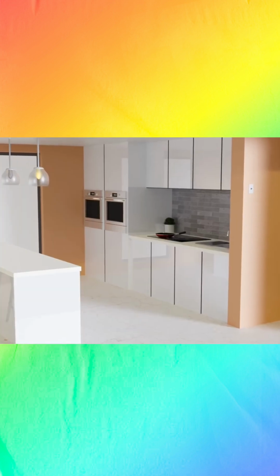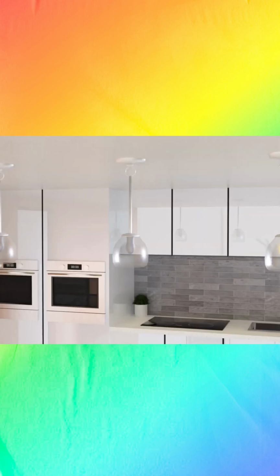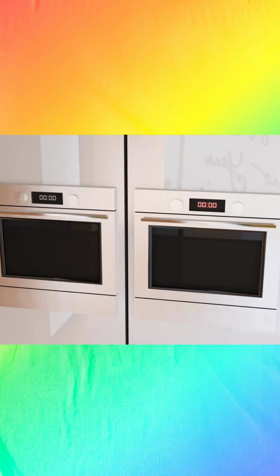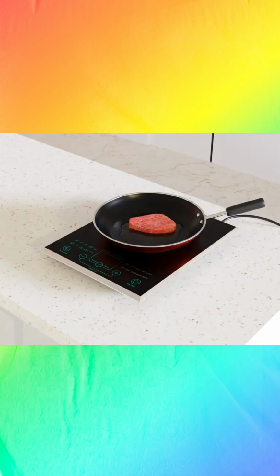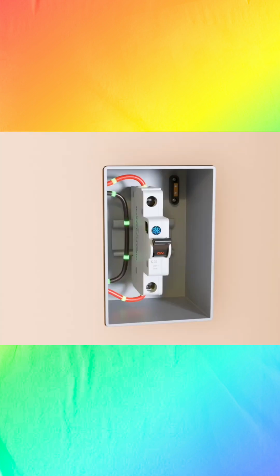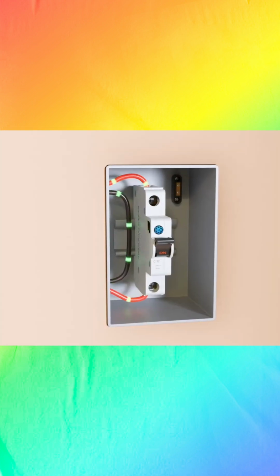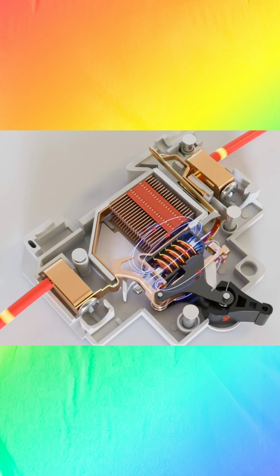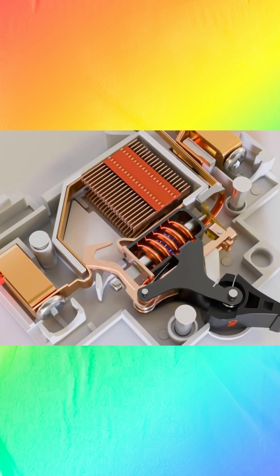But what about an overloading condition? An overloading condition happens when you use too many appliances simultaneously. This condition puts too much load on the system. As a result, the current passing through the circuit breaker goes beyond its safe limit. In an overloading condition, the current is higher than its usual amount, but not as extreme as in the short circuit condition. Because of this, the MCB is not tripped by the electromagnetic coil, as we saw in the short circuit condition. Instead, in an overloading condition, the MCB uses bimetallic strips to trip the circuit.